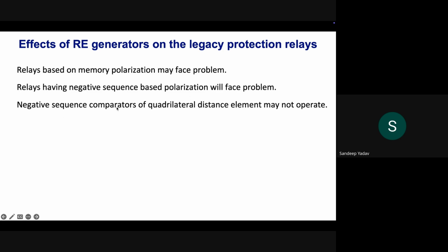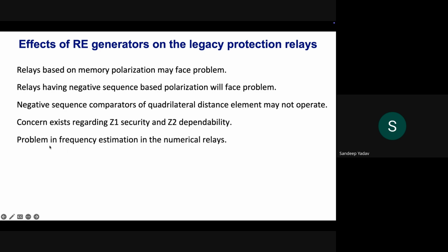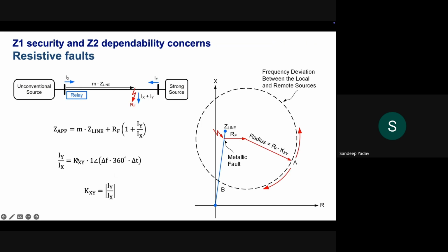The negative sequence comparators of a quad distance element, a quadrilateral distance element, will not operate at all because there is no negative sequence injection to work with. And there may be problems with the security and dependability of different zones in line impedance protection. The frequency estimation algorithms of the numerical relay will also struggle with the contribution from the RE generator side. The problems will be faced in phasor estimation. Now, when we talk about security and dependability, let's take a look at one example.